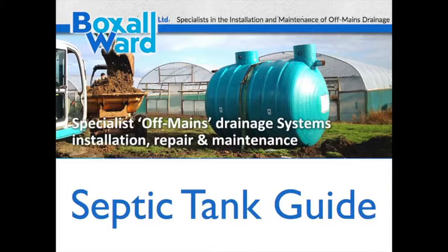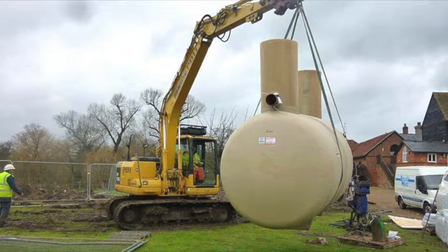They tend to be plastic tanks with a pipe at one end for incoming waste to enter the tank and another at the other end. Waste enters the tank and is then stored so that the solids, oils and greases can be separated from the liquid. Once treated thus, a second pipe at the other end of the tank releases the liquids.